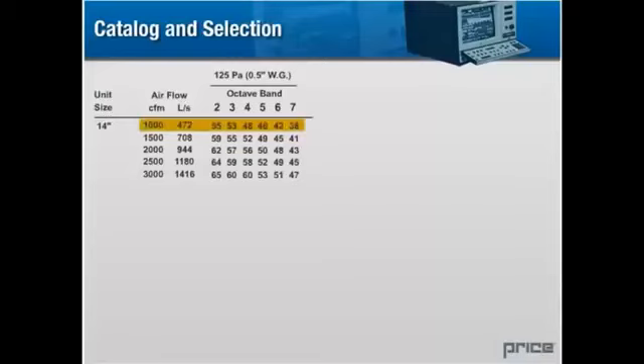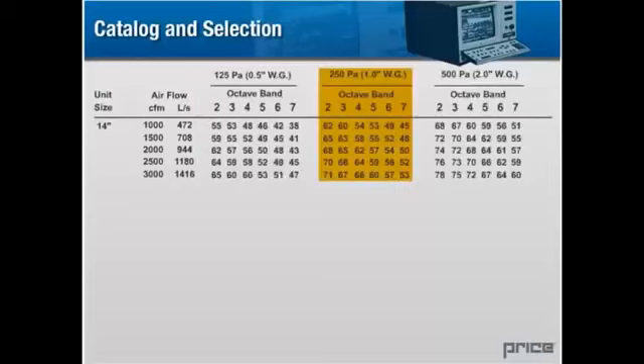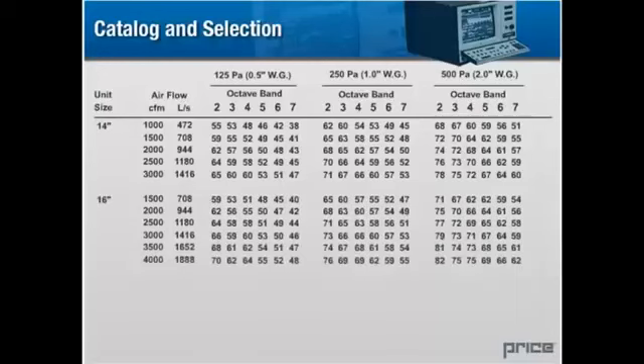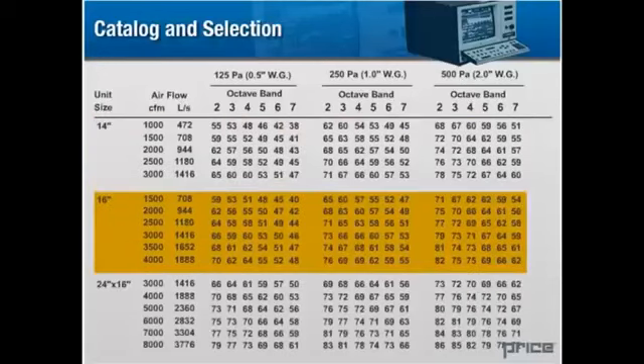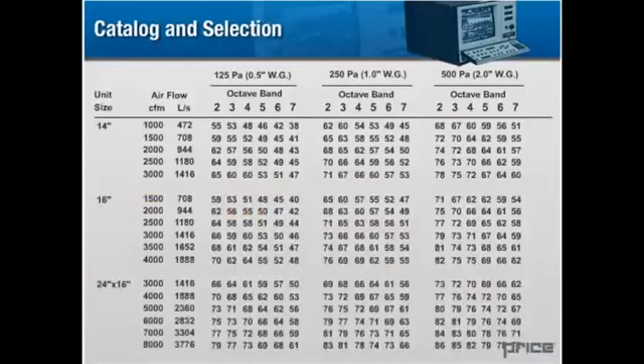Note that as we increase airflow through the terminal unit, the sound power levels increase. Likewise, the tests for static pressure drops show that as air pressure increases, sound power levels also increase. Various sizes of a product are given as well. Typically, a larger version of a particular product will be able to handle larger volumes of air without causing a significant increase in noise. Here we show a typical sound power table for terminal units that might be found in the Price catalog.